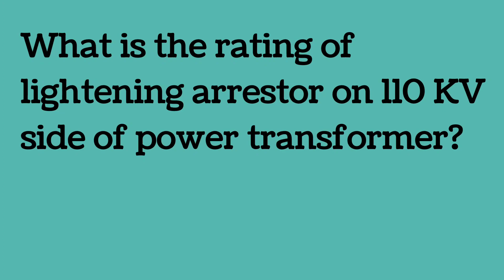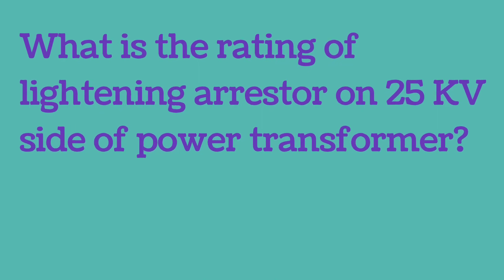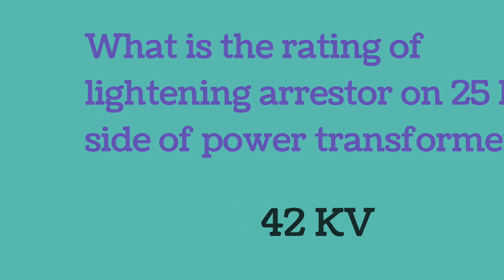The rating of lightning arrestors on the 110 kV side of the power transformer is 96 kV. The rating of the lightning arrestor on the 25 kV side of the power transformer is 42 kV.